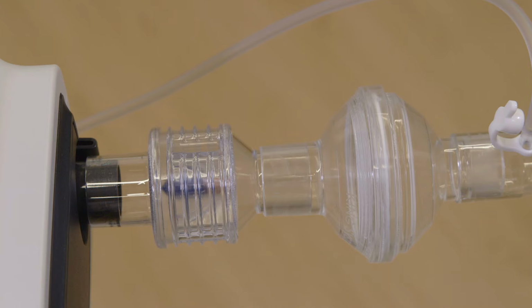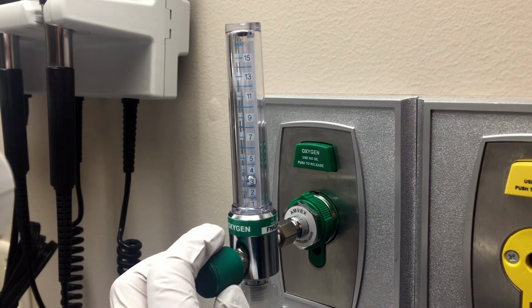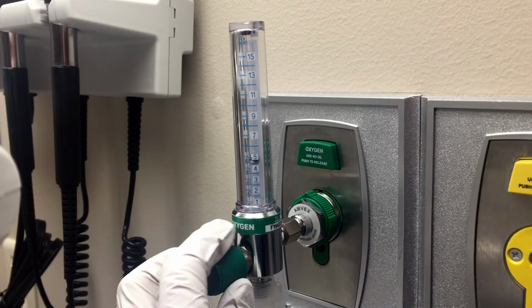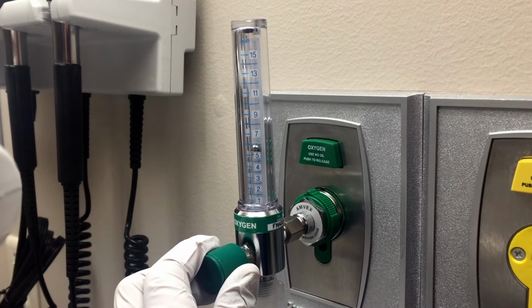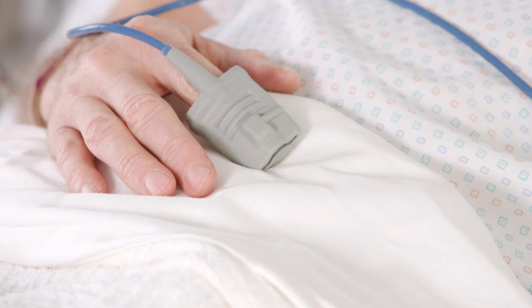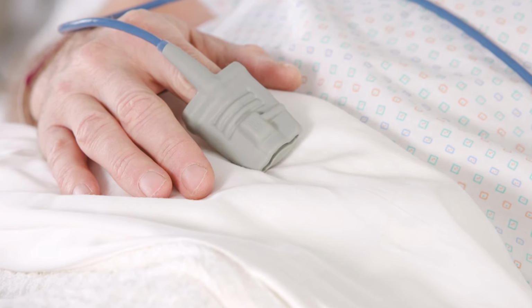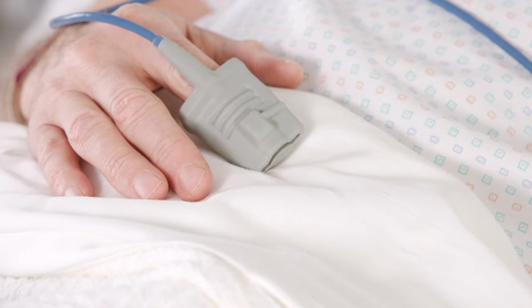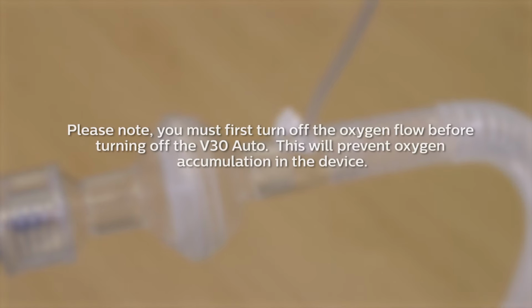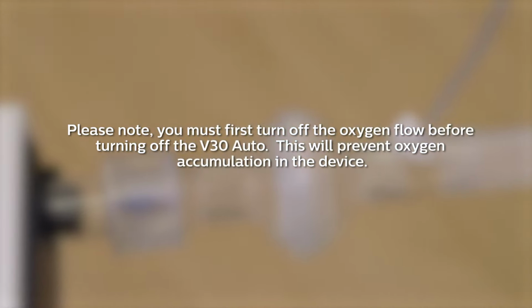Substantial leaks may reduce the inspired oxygen concentration to less than the expected delivery, so appropriate patient monitoring should be used as indicated, such as a pulse oximeter with alarm capabilities. Please note, you must first turn off the oxygen flow before turning off the V30 Auto. This will prevent oxygen accumulation in the device. If oxygen is left on and accumulates in the device enclosure, a fire hazard could be created.